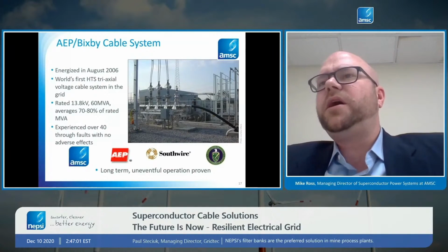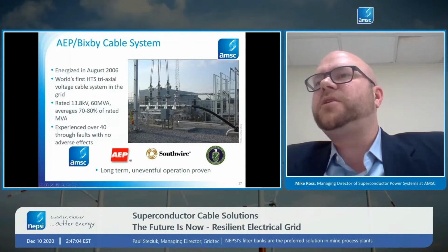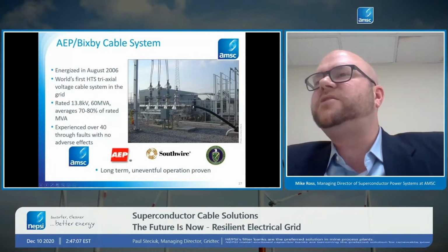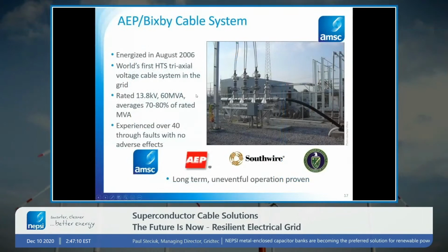A little bit of history. So this is the first superconductor cable that's using this concentric phase design, was demonstrated in the US. I mentioned this before. This was in 2006 with AEP in Ohio. This was part of a program by the Department of Energy to demonstrate superconductor cables, 13.8 kV, 60 MVA. This was installed and operated for 4 years. After 4 years, we took it apart, we chopped up the cable, we looked for any degradation. We wanted to make sure that the cable was operating and would operate for 40 to 50 years with no problems, and the entire project was incredibly successful.